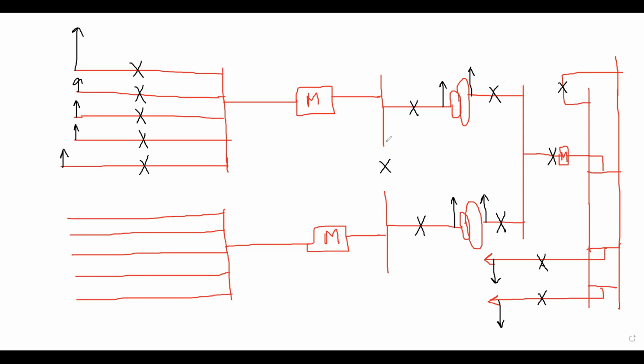Now for this breaker, what will be required? Current and voltage inputs to be given to the relay. So the relay will give the command to the breaker to open. So we need current transformers also. You can place current transformers wherever you want, on either side of the breaker. Again, in some cases it will be different. I will tell when I'm explaining about the protection class. So for this breaker to monitor, we require a current transformer. And here also we require a current transformer. Current transformer. Current transformer. And here also a current transformer.